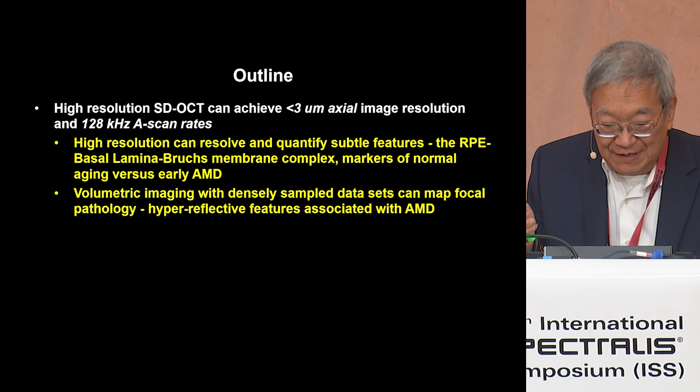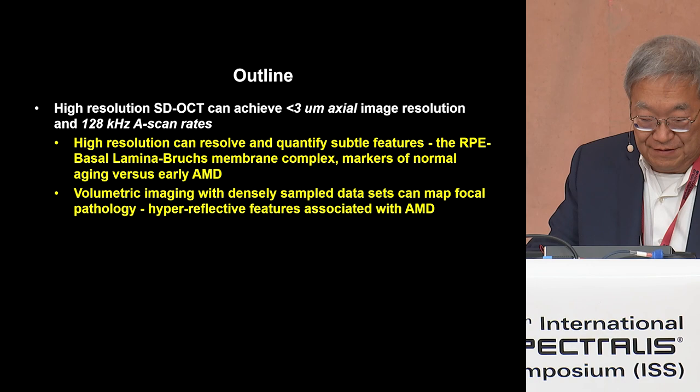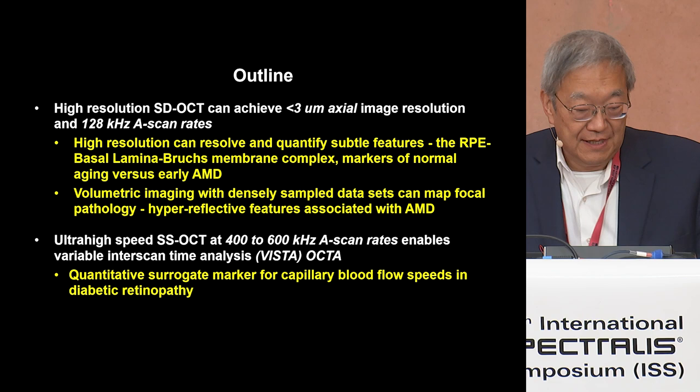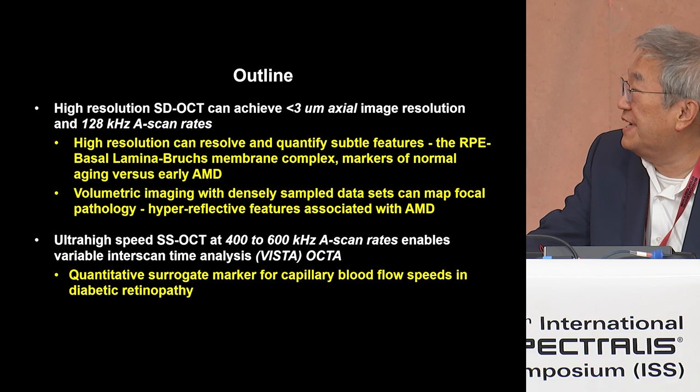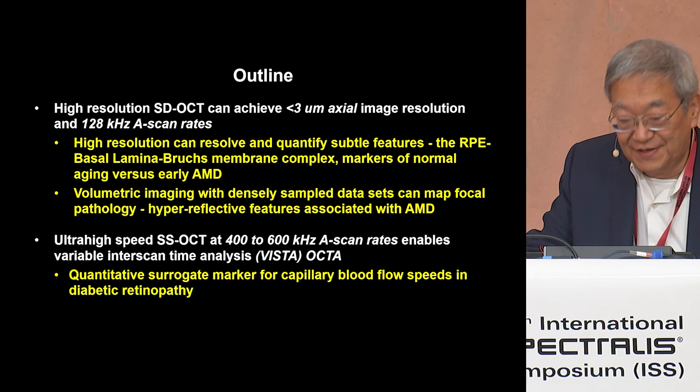This is the first part of the presentation on high-resolution OCT. The second part emphasizes ultra-high speed. In this case, we can image at 400 to 600 kilohertz axial scan rates, which are much faster than commercial systems. This is a prototype instrument, and with these types of speeds it's possible to do quantitative OCT angiography.